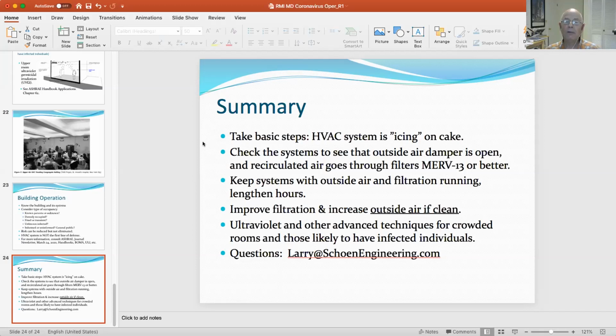For heated but non-HVAC manufacturing, are there guidelines for outdoor air? I think I mentioned that a little bit. You can use through-the-wall fans to bring air in. I've given you some CFM per person numbers. The thing you want to be careful about is that you're not blowing air from dirty to clean. So for instance, locate that fan in a place where it's not a high contaminant area, whether those contaminants are from the manufacturing process itself or from the possibility of disease. You don't want to blow from a dirty area to a clean one. So try to take the air from a clean area and inject it into a clean area in your facility, so that that clean air is getting to the other areas in the facility.